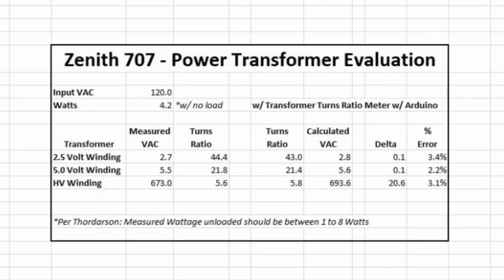Here's the basic spreadsheet that I referenced. You can see I used my variac, set my input voltage for 120, measured the wattage at 4.2 watts, again no load. If you look down at the bottom, I have a note there as well: it's recommended that the measured wattage unloaded should always fall between 1 and 8 watts. So I think we're good there on the transformer.